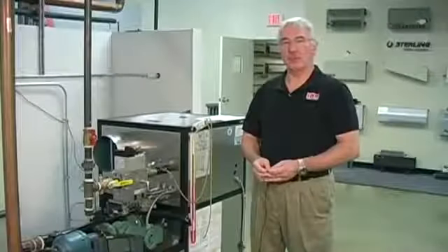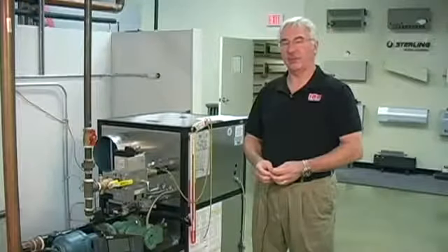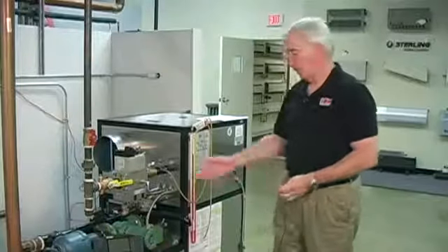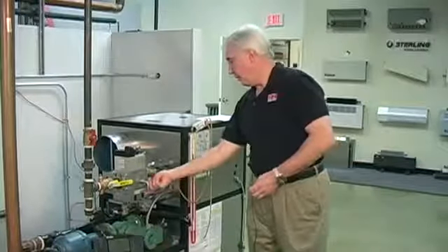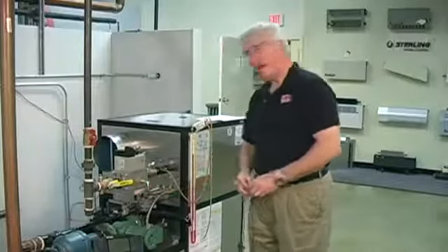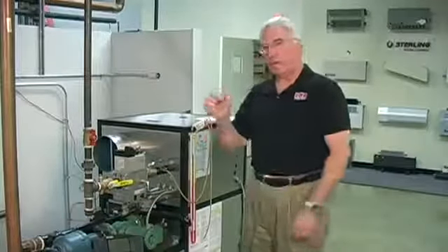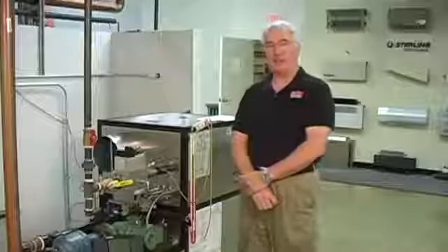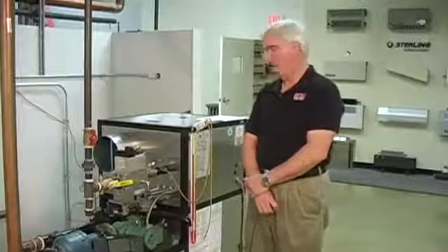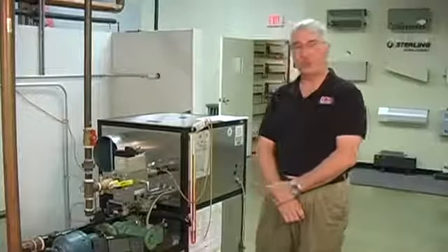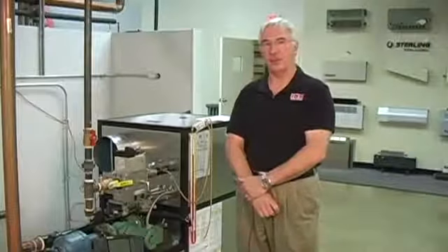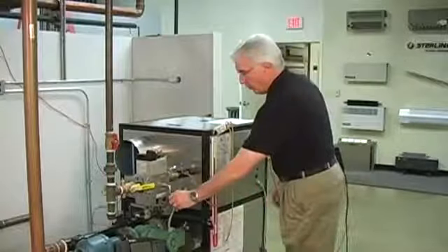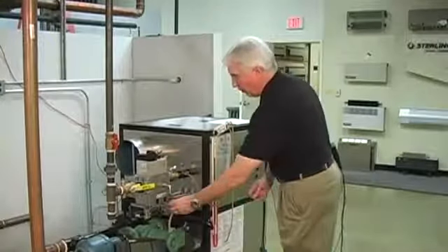If you find that your combustion readings on low fire are not within the parameters listed in the installation and operations manual, you might have to make an adjustment. To accommodate that adjustment, the gas valve has an adjustment port on the lower right hand corner. Using a small Allen wrench, you insert that into the little hex on the valve and rotate it clockwise to increase the gas or counterclockwise to decrease it. Again, you want to use your combustion analyzer as a guideline as to where you're going to end up. Once you're satisfied with that reading, you can remove the wrench and close up your little plug there.